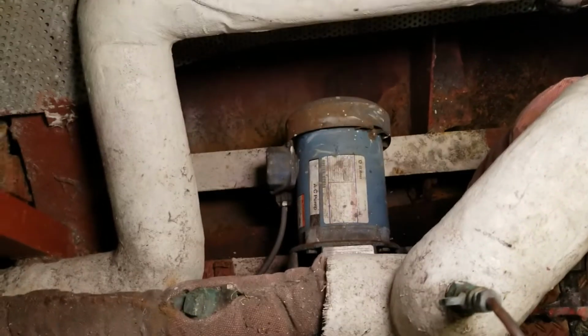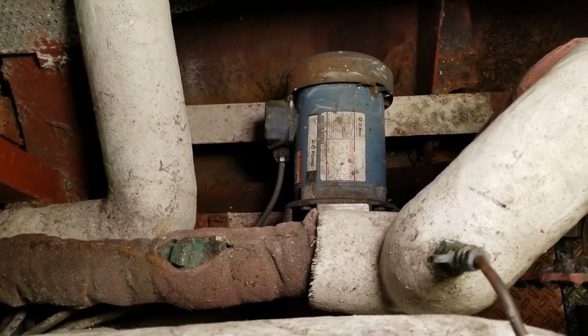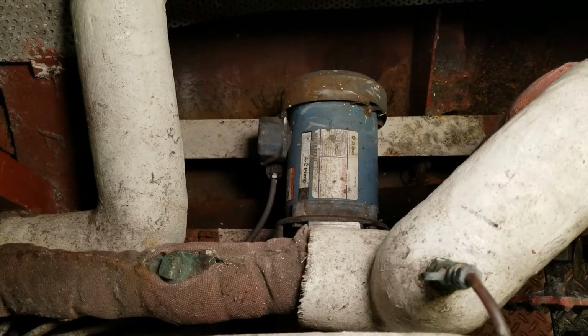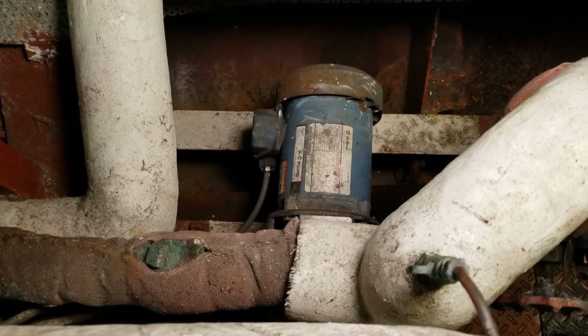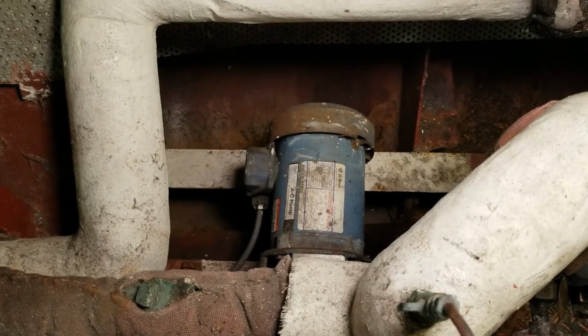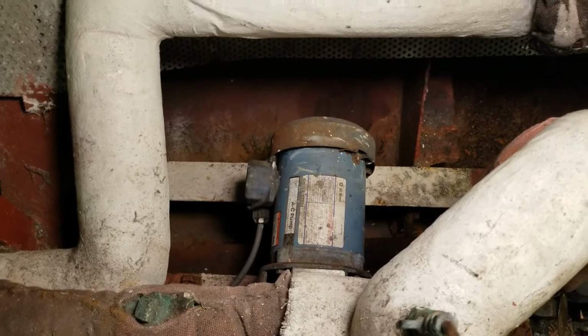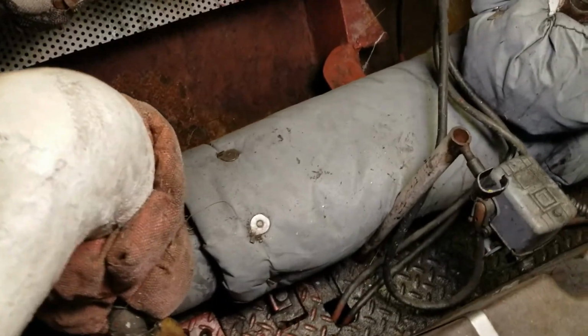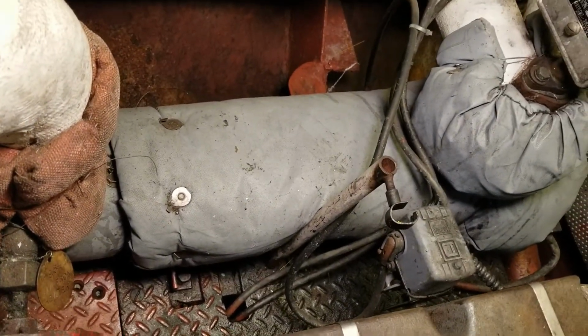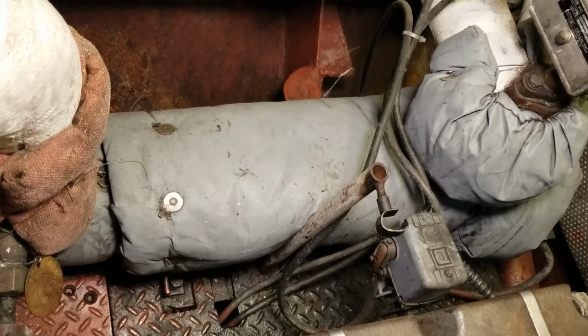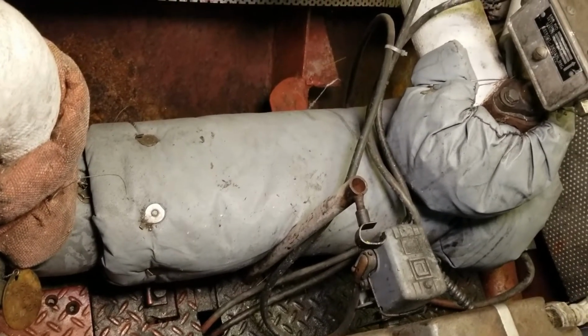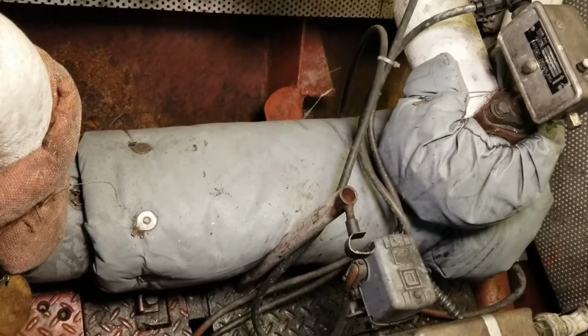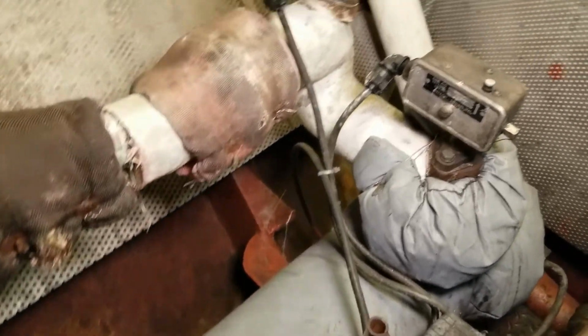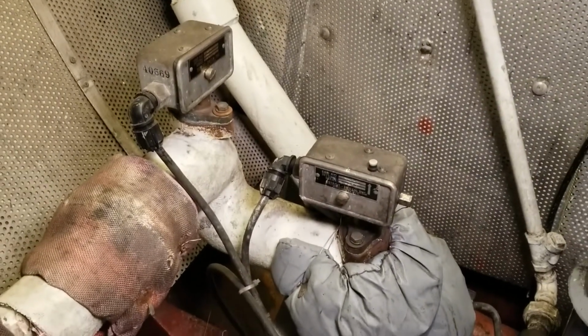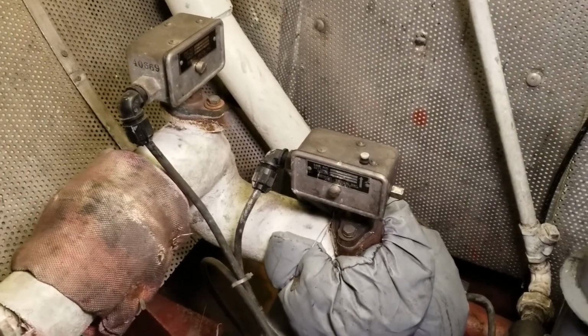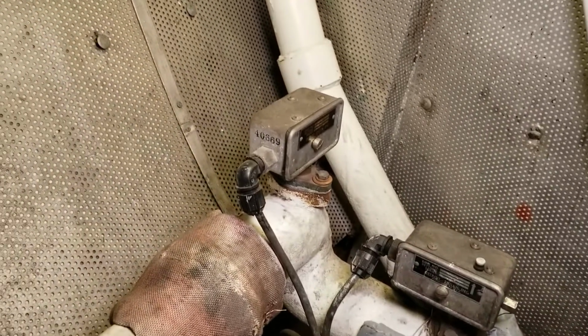We're on the lower level, starboard side. There's our circulating jacket water pump, which is part of the immersion heater system. That's circulating jacket water through the circuit, through the lube oil heater / heat exchanger, and it's also circulating jacket water through this immersion heater, which is covered by a lagging pad right there. That gray pad. Underneath that gray pad, it's just a water heater. And the two temperature switches are right there in the circuit. So there's the first one right about mid-screen, and there's the second one.